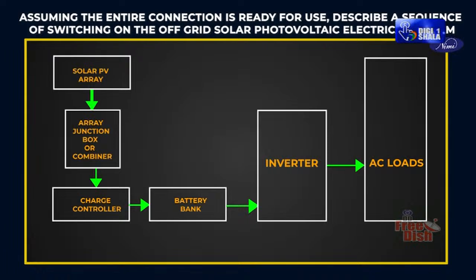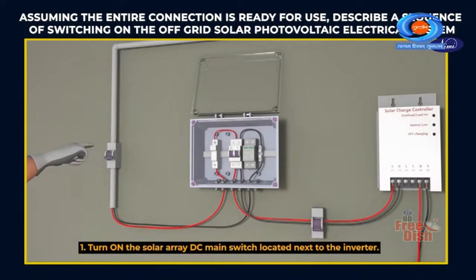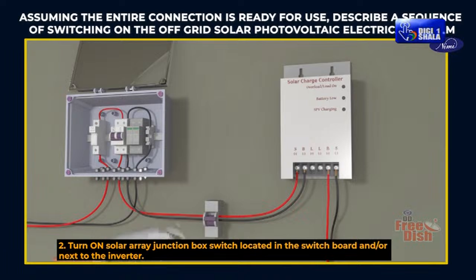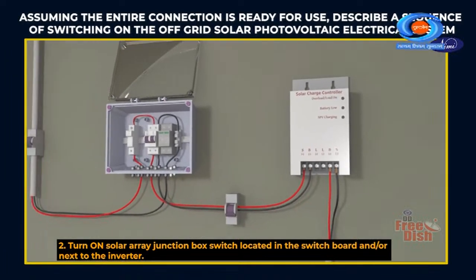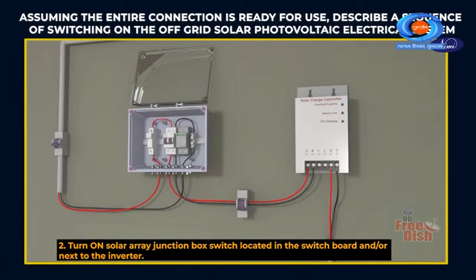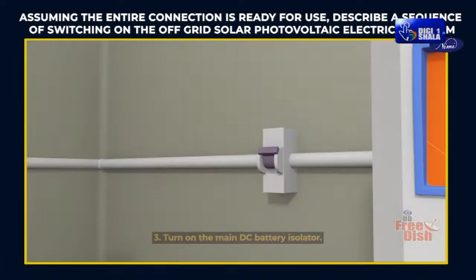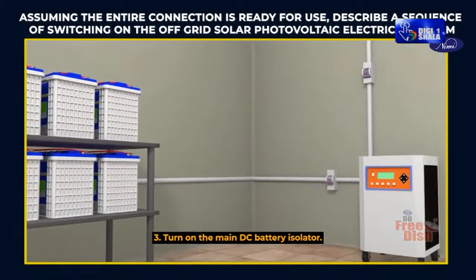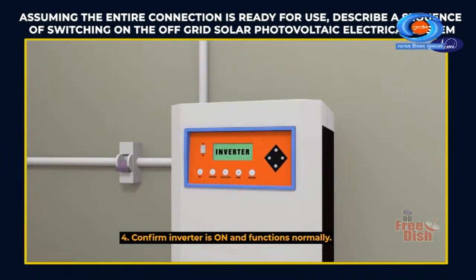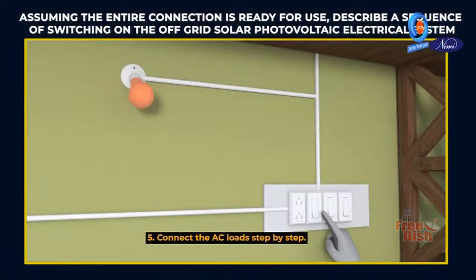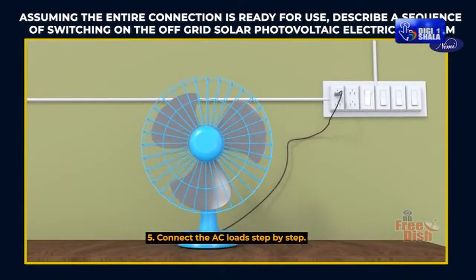Assuming the entire connection is ready for use, describe a sequence of switching on the off-grid solar photovoltaic electrical system. Sequence of switching on. Turn on the solar array DC main switch located next to the inverter. Turn on solar array junction box switch located in the switchboard and/or next to the inverter. Turn on the main DC battery isolator. Confirm inverter is on and functions normally. Connect the AC loads step by step.